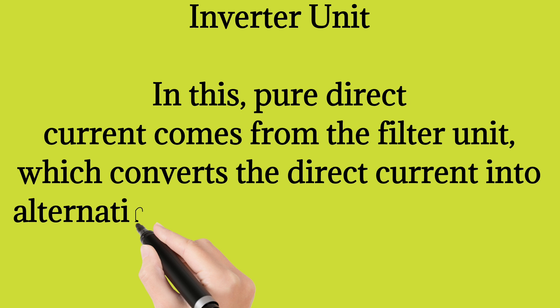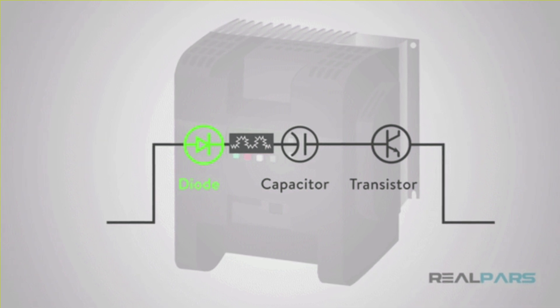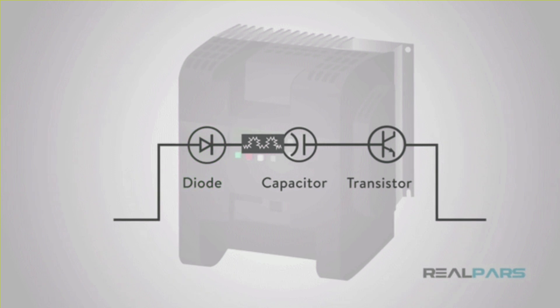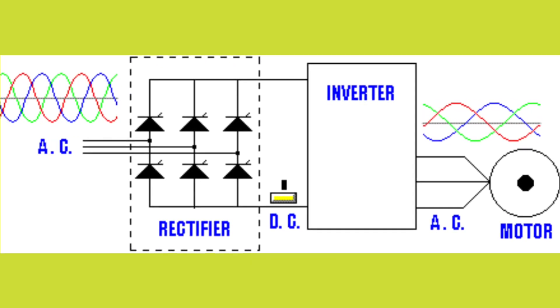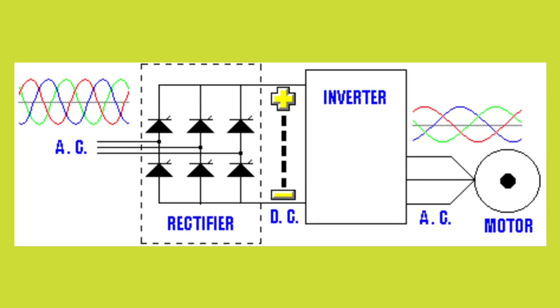How VFD or AC drive works: according to the VFD or AC drive working principle, it is an electronic controller specially designed to change the frequency of voltage supplied to the induction motor. A VFD controls the speed of an AC motor by varying the frequency supplied to the motor. The first step is to convert the AC supply voltage to DC using a rectifier. DC power has voltage ripple which is eliminated by using a filter capacitor, then the DC voltage is converted into AC voltage with the help of an inverter, which is our output.